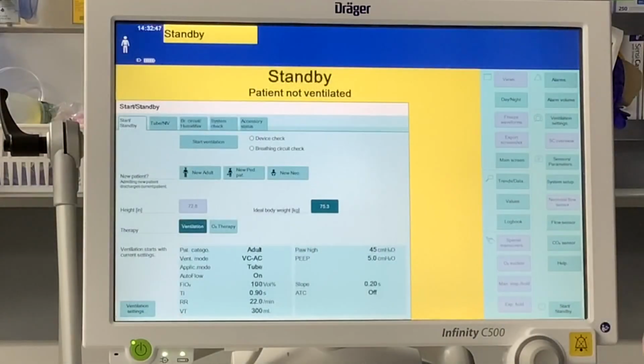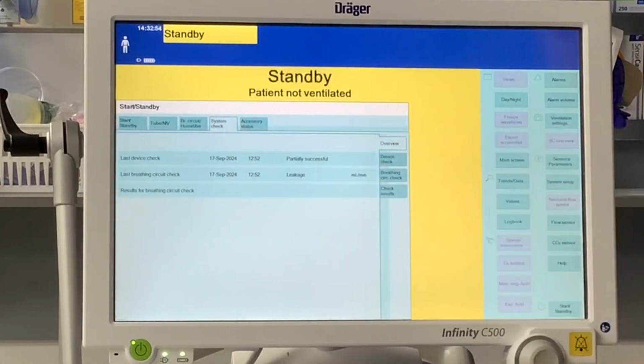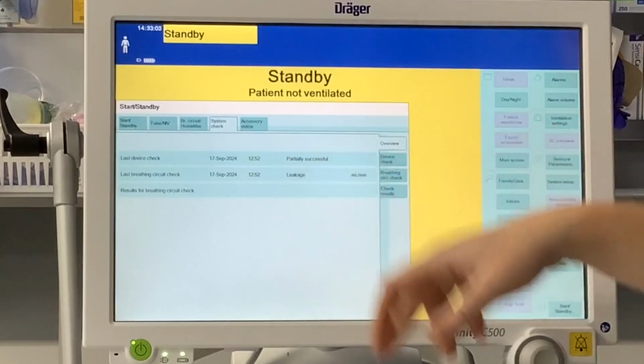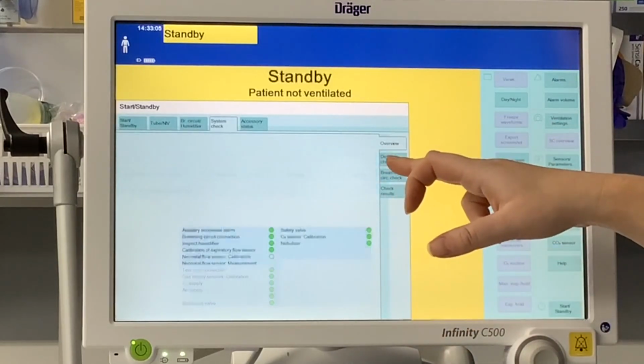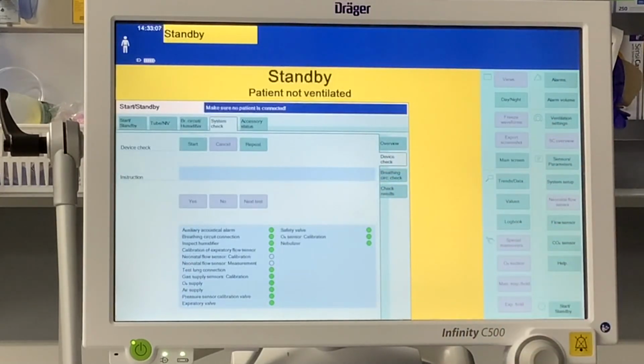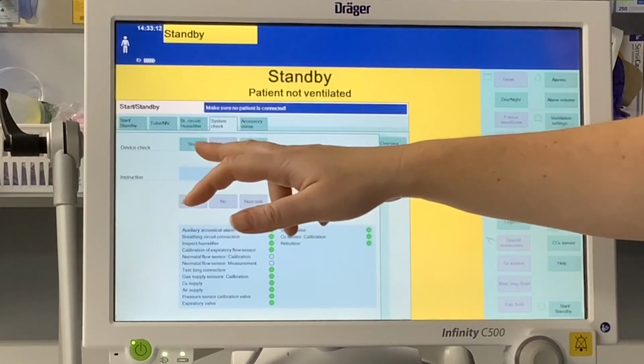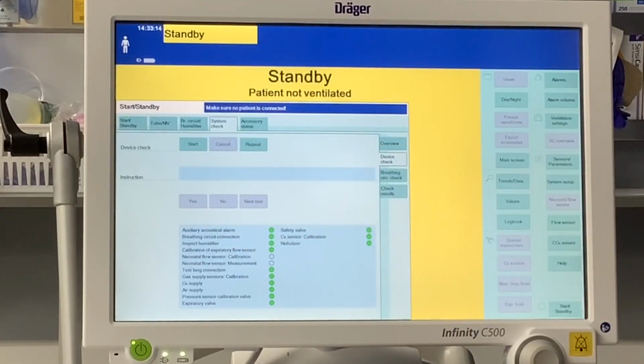So we are going to do a vent checkout. What we're going to do is go into system check. It's going to tell us in here when the last check was. So we're going to go into device check, start there, and all we're literally going to do is press start. You do have to have the vent plugged in, obviously, and you have to have air and oxygen hooked up for this.